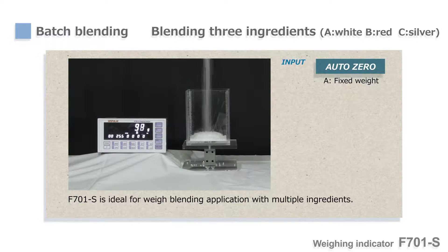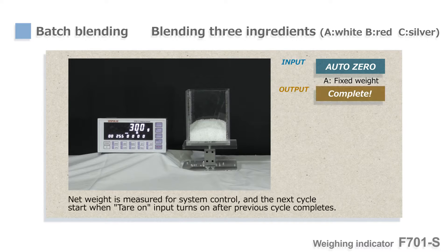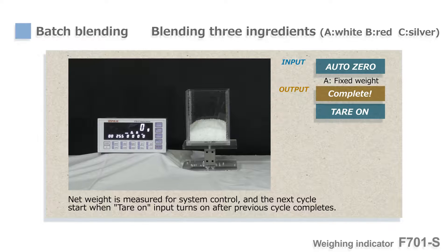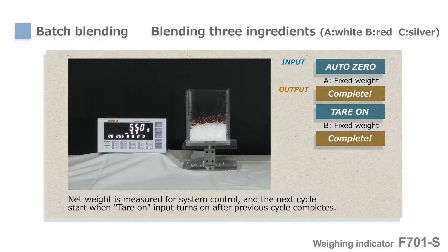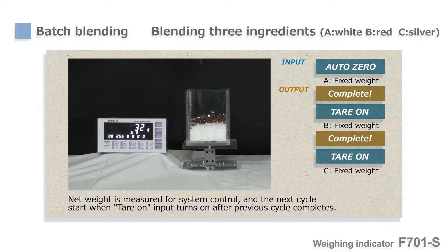Next application is weight batching or blending. At first, an empty container is placed on the scale and tare feature is used to set weight to zero. Then, material A is filled up to the preset weight level. After the first cycle, tare weight feature is turned on before the next weighing cycle for material B starts. Then material B and C can be filled up to each preset weight in the same way.